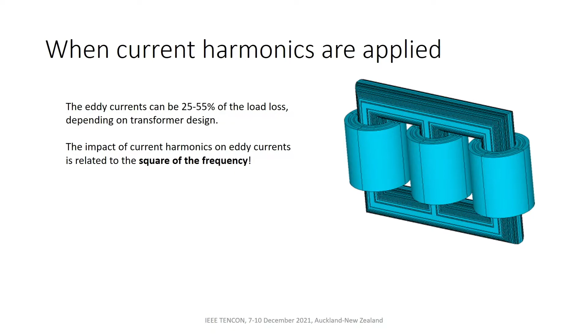In terms of the IEC standards for transformers, they state the total harmonic distortion of current should be no greater than 5% at the rated transformer load for normal service conditions. The transformer standards do give us an option: if higher harmonics are present, a solution is to derate the transformer. It's worth pointing out that the standards for transformers, the 60076 series, are only considering the transformer. They do not consider what else is happening on the network. That's usually more in the 61000 series, which discusses the power quality acceptable for the system itself, and the utilities may also have their own power quality requirements.